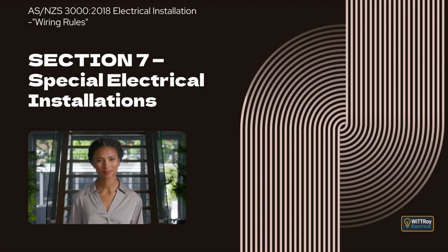Where cabling passes through areas with different protection requirements, the highest level of protection must be applied unless it is not practical to do so. The clause then explains exceptions where fire protection requirements do not apply, such as wiring installed in locations that already provide protection, certain battery-backed emergency systems, and wiring for electric-driven fire pumps that are part of a larger pump arrangement. Clause 7.2.2.2 Wiring Systems. This clause explains that wiring systems supplying safety services, including their supports, must comply with the relevant wiring system standard and the required wiring system classification, depending on what equipment is being supplied and where it is installed.